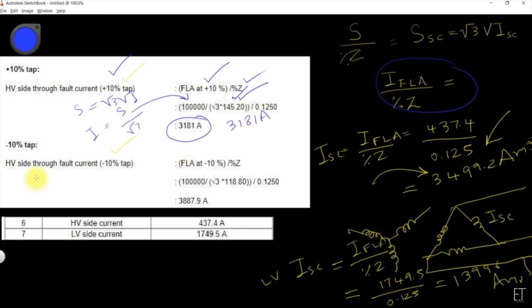In the same way we calculate the short circuit current when the tap is at minus 10%. Again you take the full load amperes at the HV side and make it minus 10%. Using the same formula, under root 3 V into I, V here is chosen at minus 10%, that is 118.8 kV, and you divide by the percentage impedance, which is 0.125, so you will get these two currents. Now we have done the calculations of through fault or short circuit current at plus 10% tap and minus 10% tap. Thank you very much.